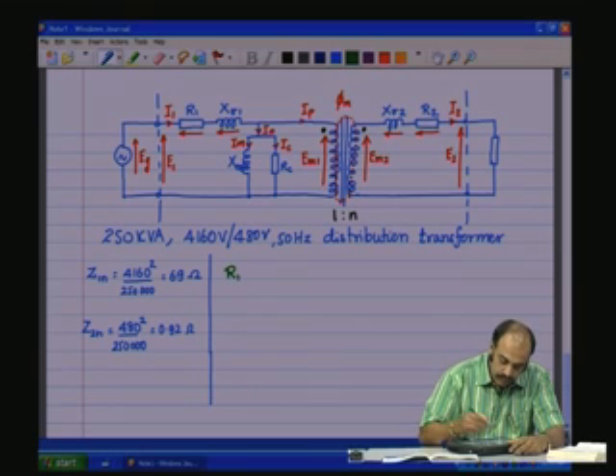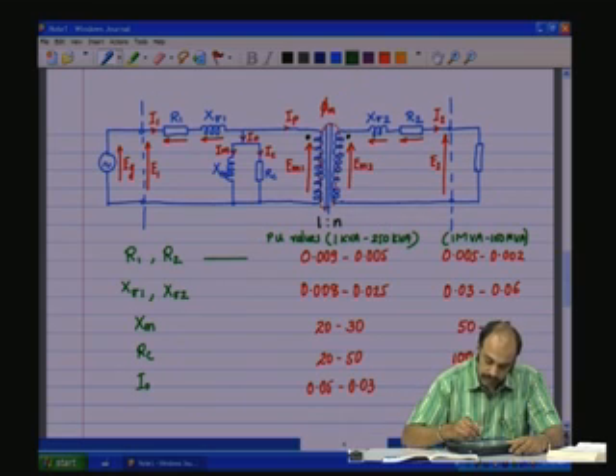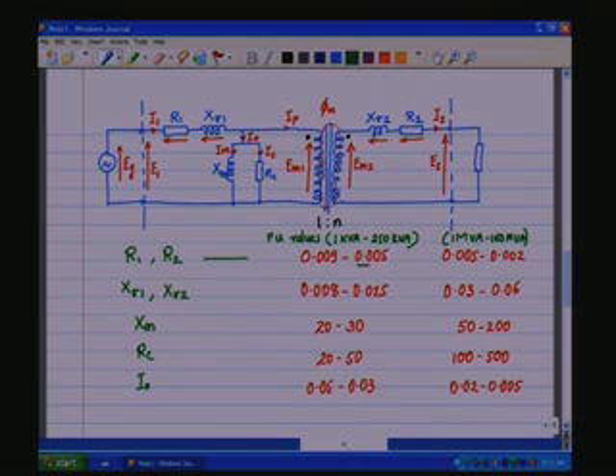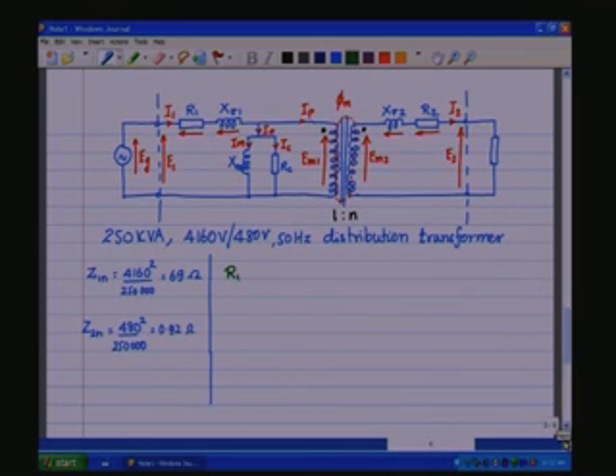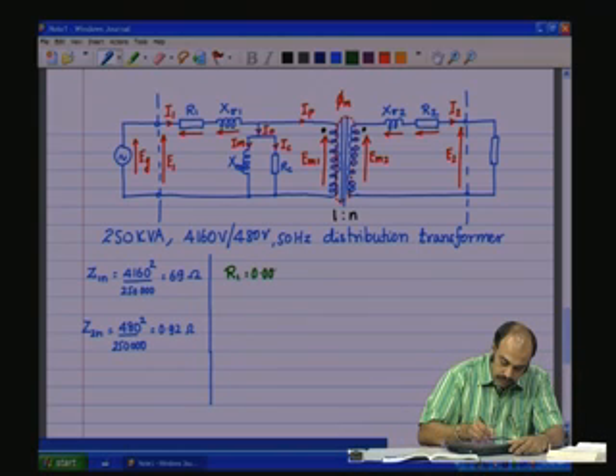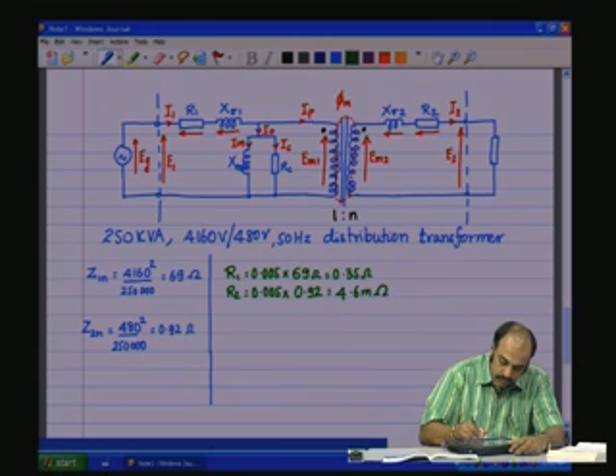So, now R1. We look at the table, and we are talking of the 250 kVA transformer, and therefore let us take these values for consideration. So, R1 and R2, the per unit value is 0.005. So, R1 is 0.005 into the base impedance on the primary side, 69 ohms, which is 0.35 ohms. R2 is again 0.005, and the base impedance on the secondary side is 0.92, which gives you 4.6 milli ohms.